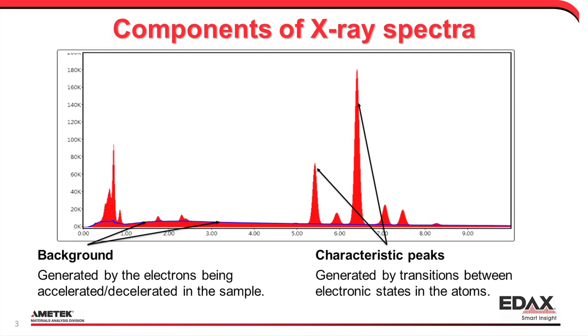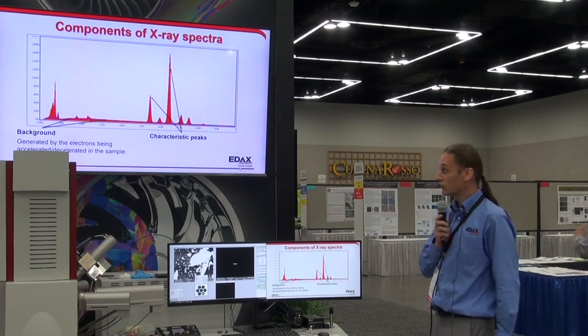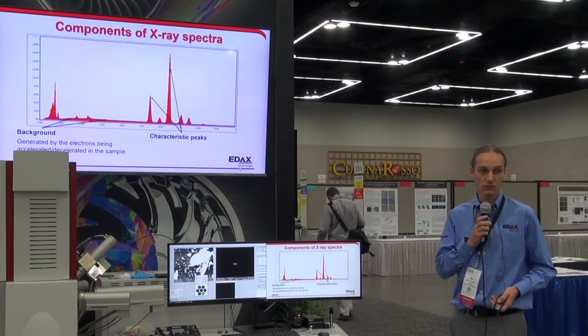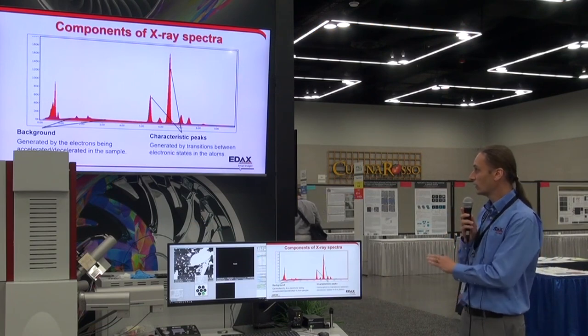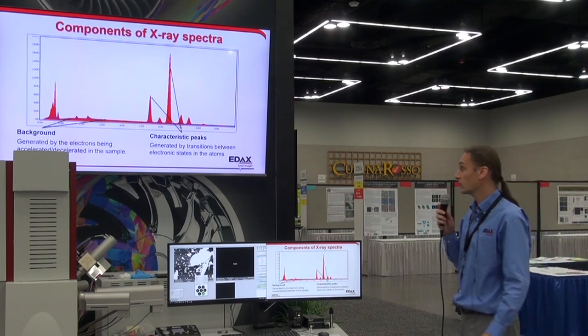If we look at a spectrum, we have a background and we have some characteristic peaks. Most of the time we only care about the characteristic peaks — what elements are in the sample. But the background holds a lot of information as well. The background is generated by electrons being slowed down or accelerated as they move through the sample and emitting radiation, whereas the characteristic peaks are generated by transitions between electronic states within the atoms.